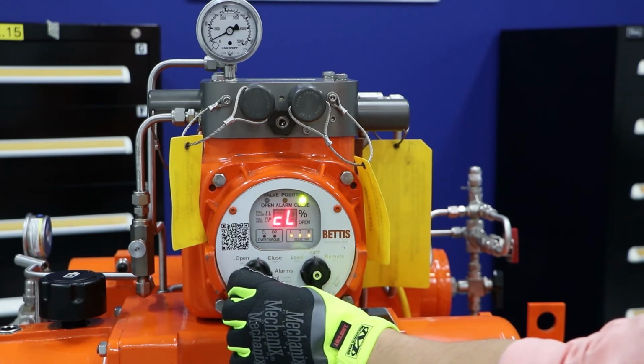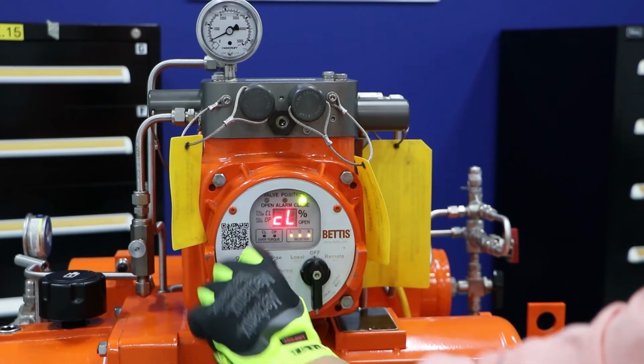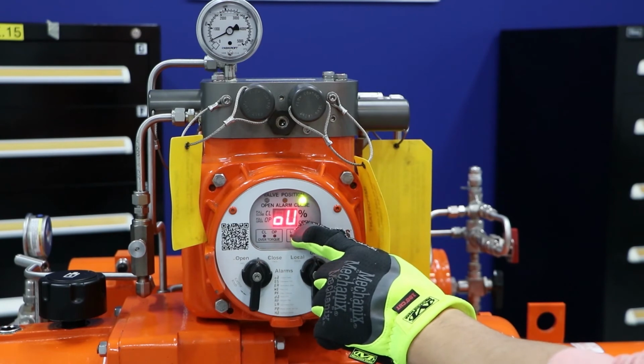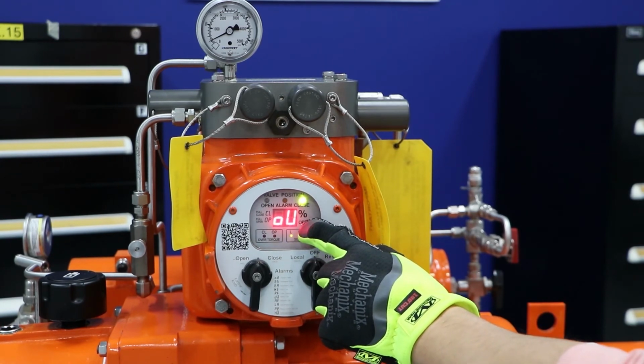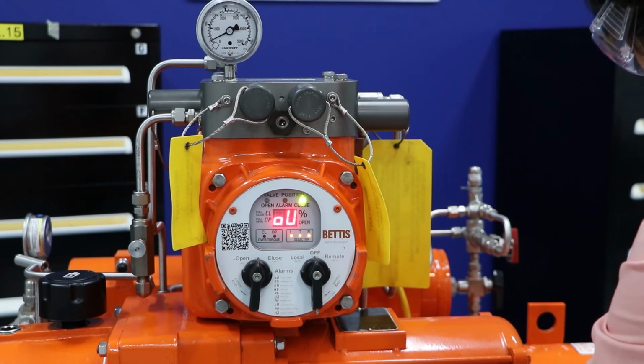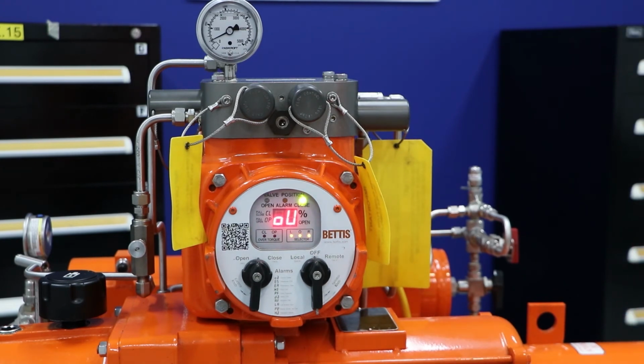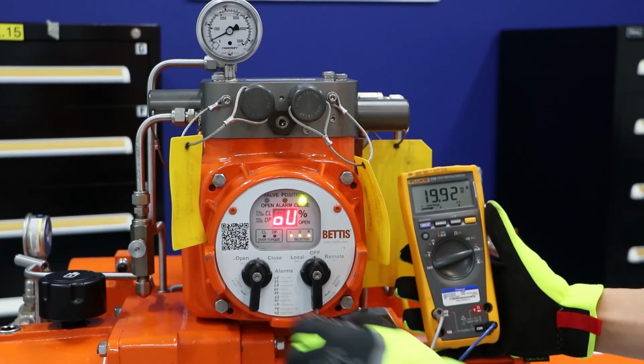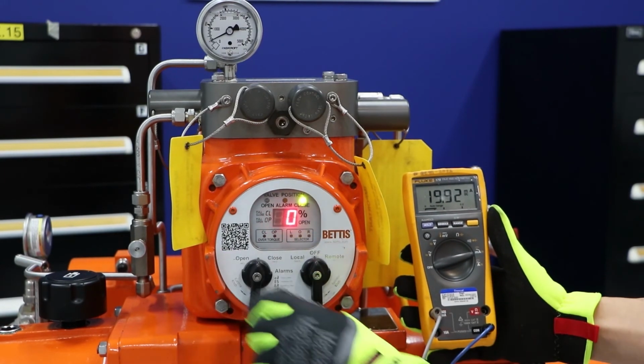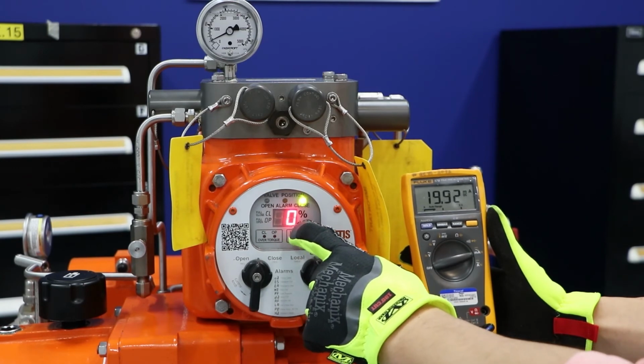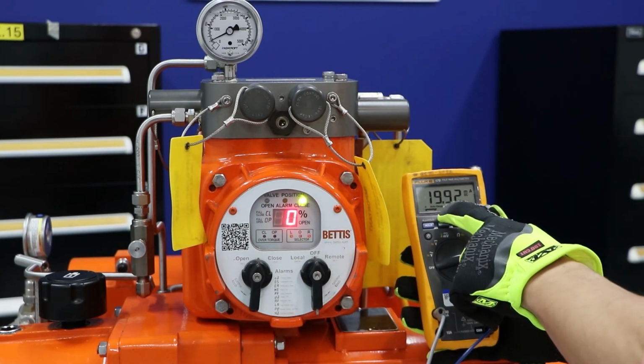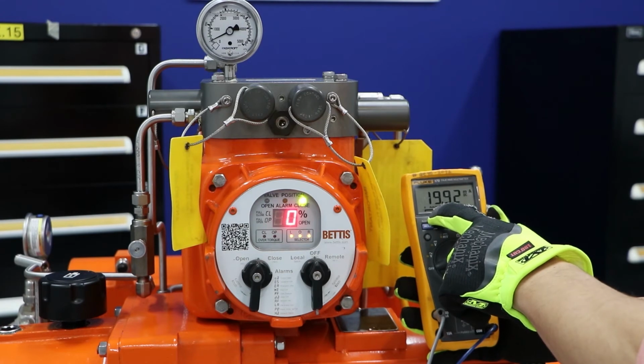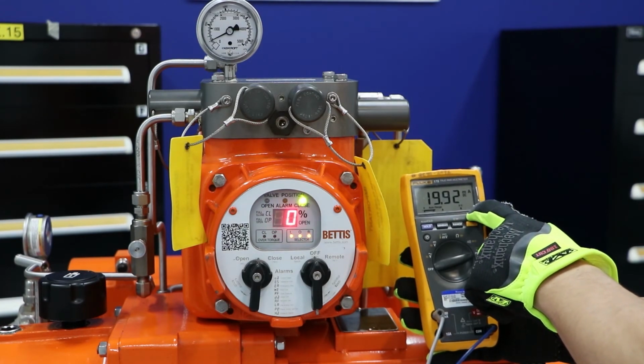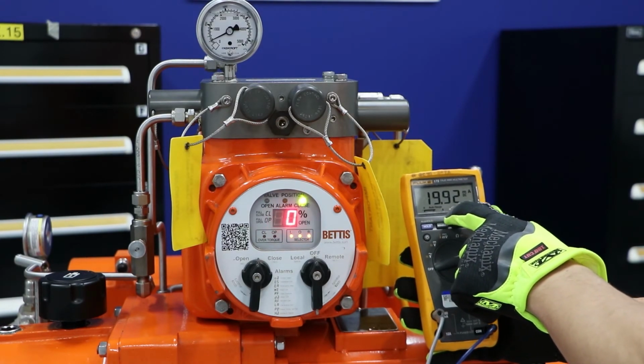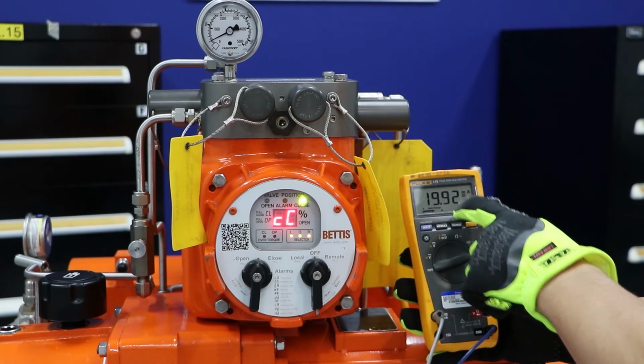Now, in order to set our upper limit, we'll hit yes here, and now it jumps to OU, which is our upper limit. And we want to follow the similar procedure as we did before, but instead of 4 milliamps, we want to do 20 milliamps. So we'll hit yes here. Now we see CC is 0. And in this case, our multimeter reads 19.92. We want it to be 20.00.